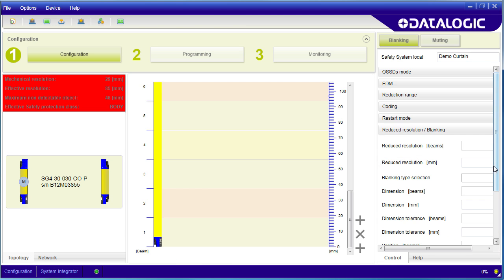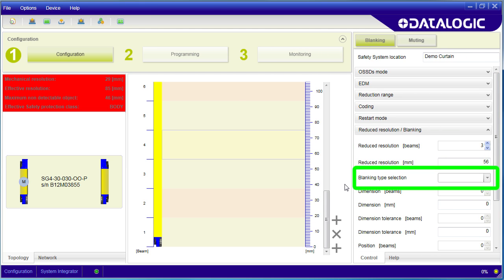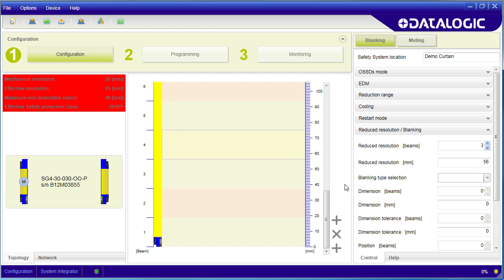So resolution determined how small of an object we could detect. Blanking says ignore certain beams. Maybe you have a fixed part of a machine that will always be blocking one or more sections of the light curtain. Well, you can just turn off those beams or blank those beams. Resolution has to be zero to do this, so let's change that back.